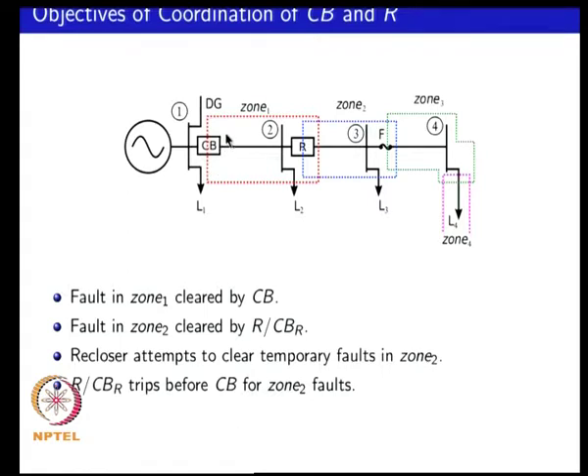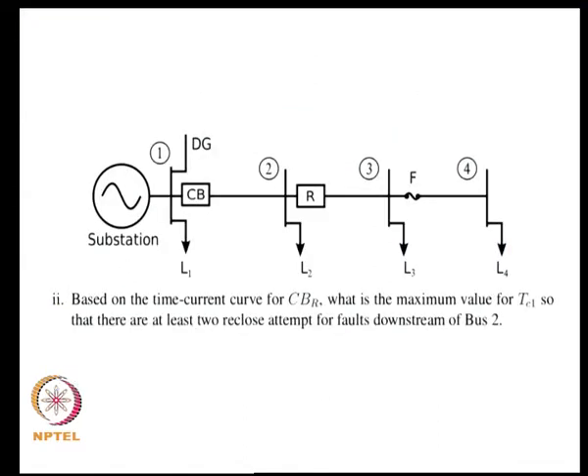If there is a permanent fault in zone 2, one has to ensure that the recloser locks out before the upstream circuit breaker trips. That is the overall objective for this coordination problem. Based on the time current curves for the underlying circuit breaker of the recloser and for the upstream breaker, we find the timings required for the recloser.